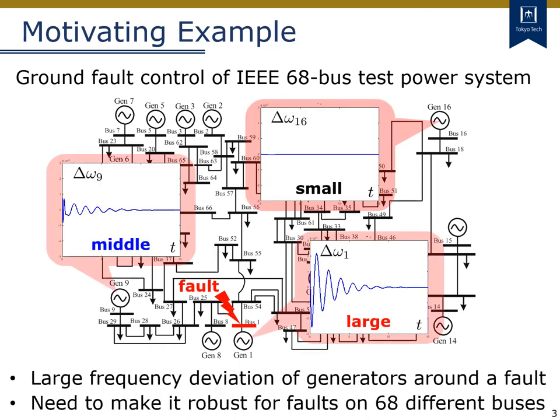Such faults may occur in the real world by thunderbolts falling on some facilities of power generation and transmission. A simulation result is shown when a ground fault occurs on the first bus. As you can see, large frequency deviation of generators occurs close to the bus fault, while small frequency deviation occurs for generators distant from the bus fault. The control objective is to reduce the magnitude of frequency deviations of generators due to such bus faults, by suitably controlling the excitation system in each generator.